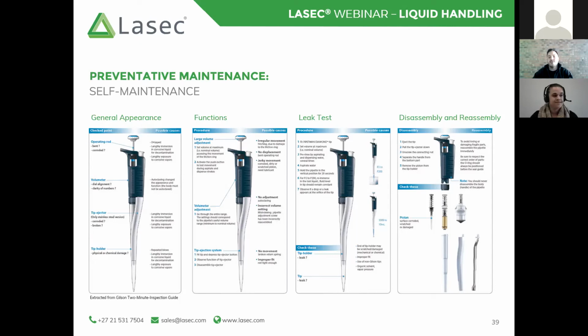If at this stage you do realize that it's incredibly difficult to depress that push button, or that the push button does not return to its rest position once you release any pressure, that's an indication that a mechanism inside the pipette is damaged and rendering that pipette unusable, meaning that it would need to be serviced or that parts would need to be replaced.